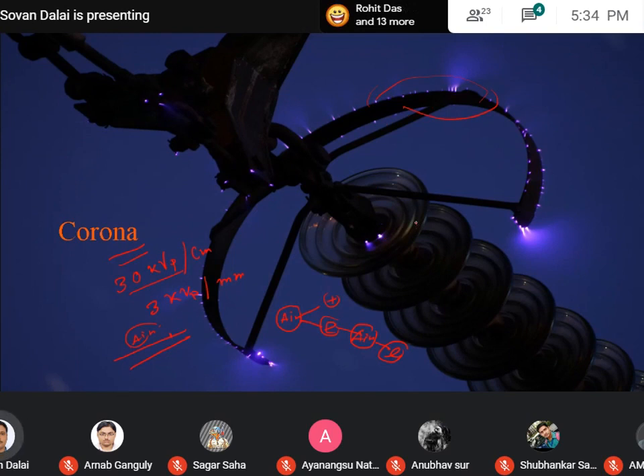What does it affect? A huge amount of power loss is involved due to that effect. So you have to avoid that corona. To avoid corona, you have to maintain the electric field intensity over the surface of the conductor, or any portion of the conductor or the tower, so that it does not exceed 30 kV peak per centimeter. But this is at a certain temperature and pressure, which may vary depending upon the weather condition.